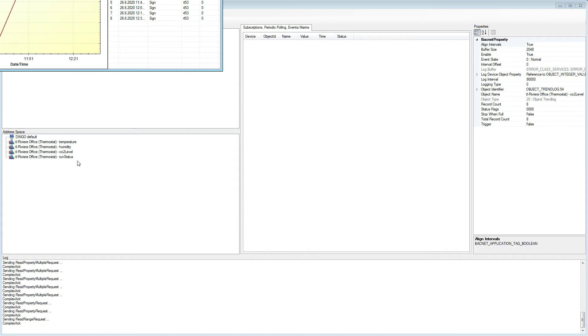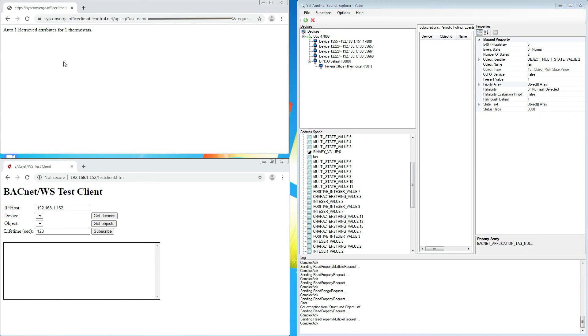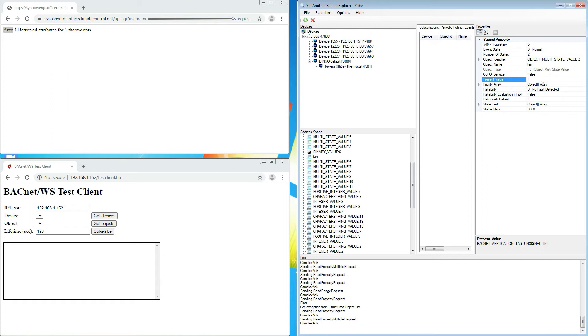We can also write values back to the Pelican climate control API via the BACnet objects. Here in my browser, I am reading a fan property directly from the Pelican climate control API and we see that it is configured to auto. In Yabe, we can read the same property as a BACnet object and we see that its present value reads 1, which means it is on auto.